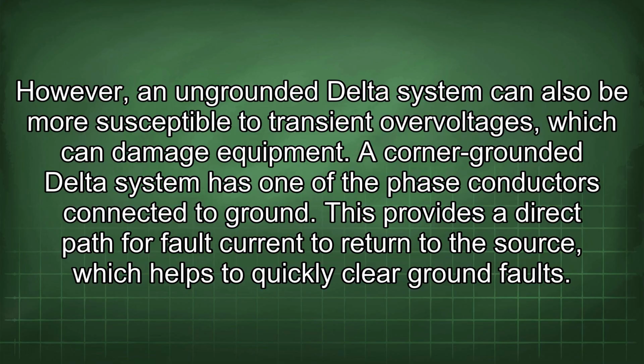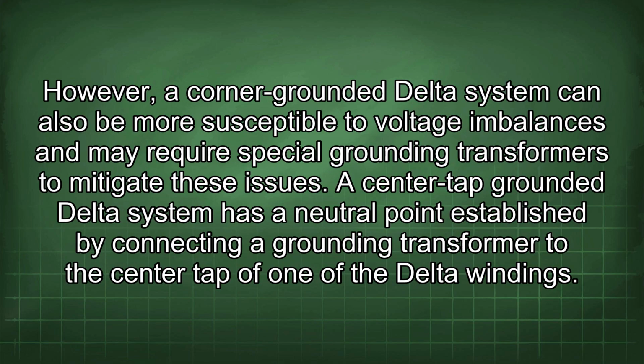A corner grounded delta system has one of the phase conductors connected to ground. This provides a direct path for fault current to return to the source, which helps to quickly clear ground faults.